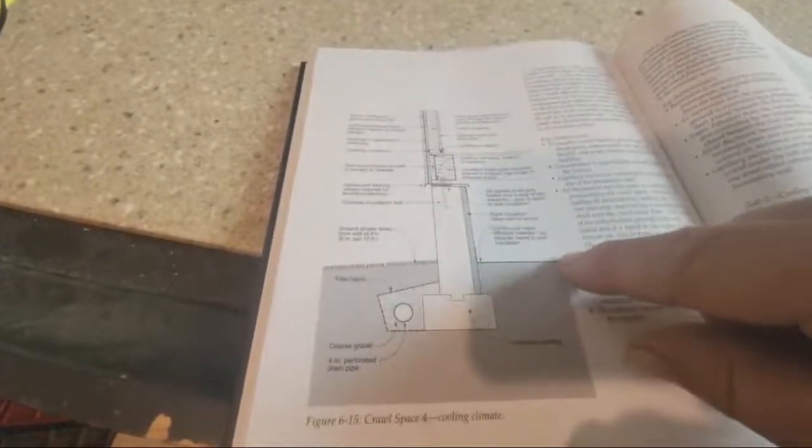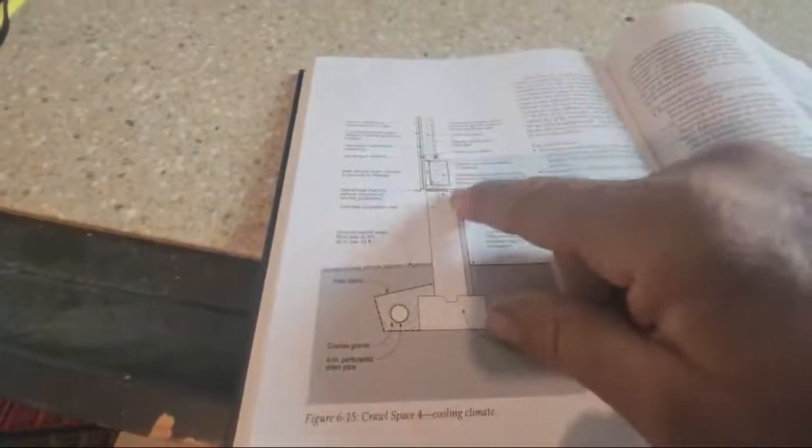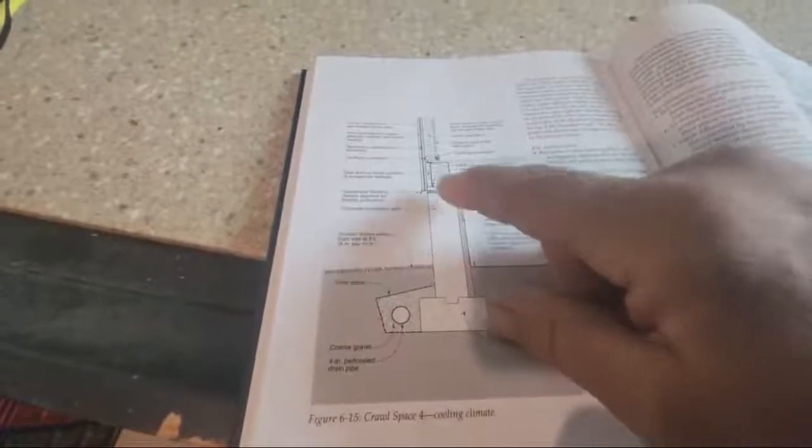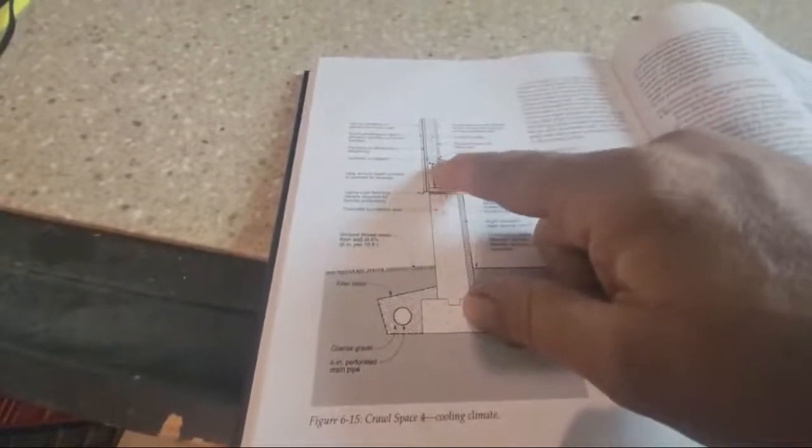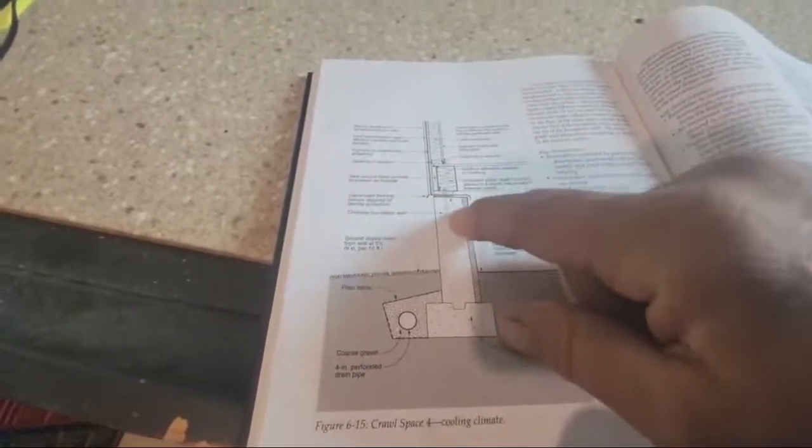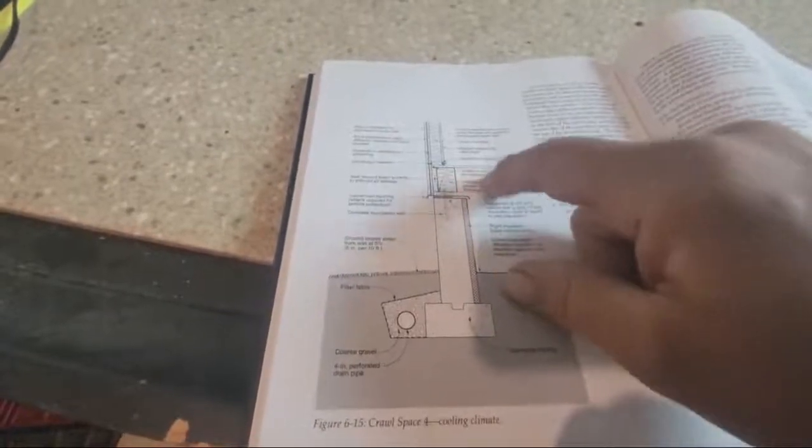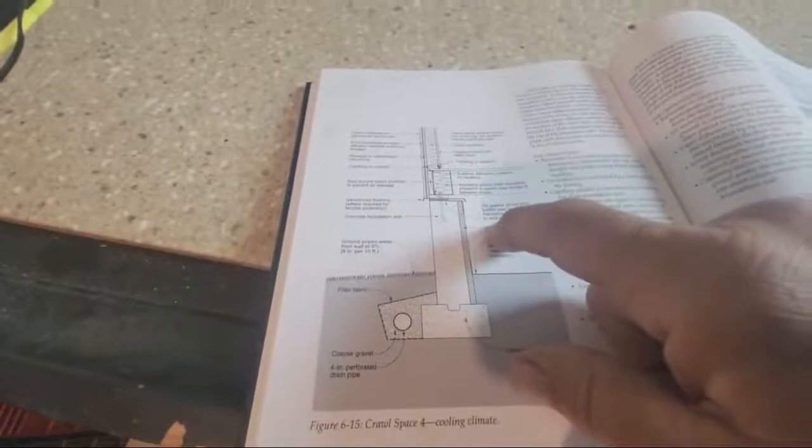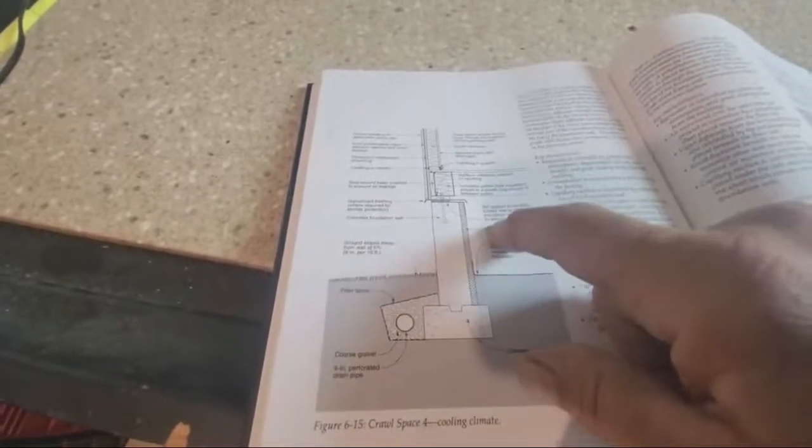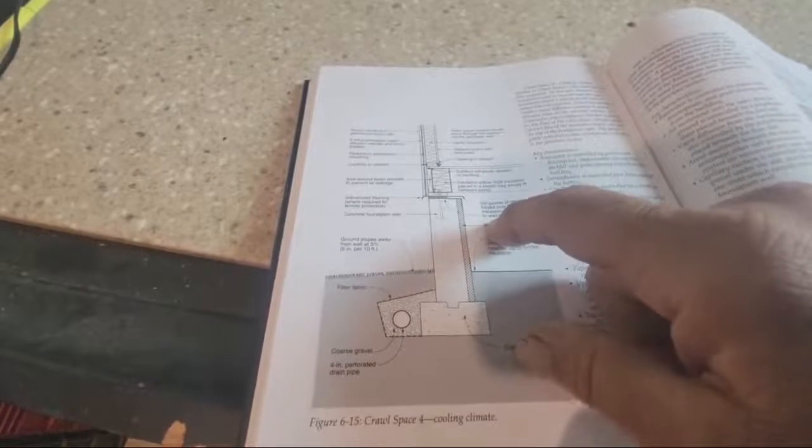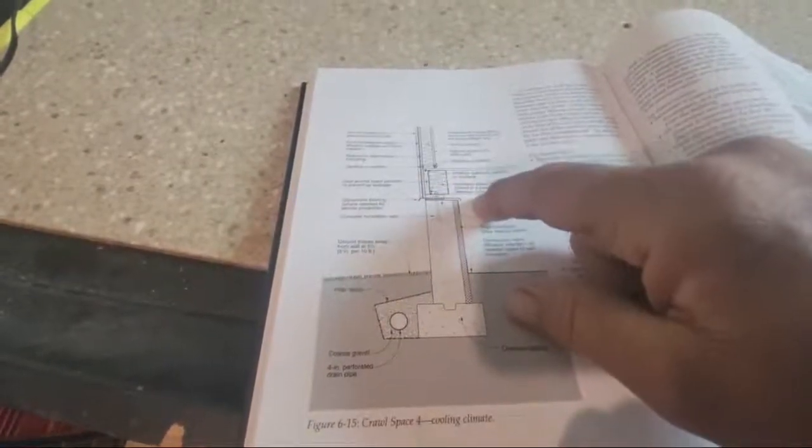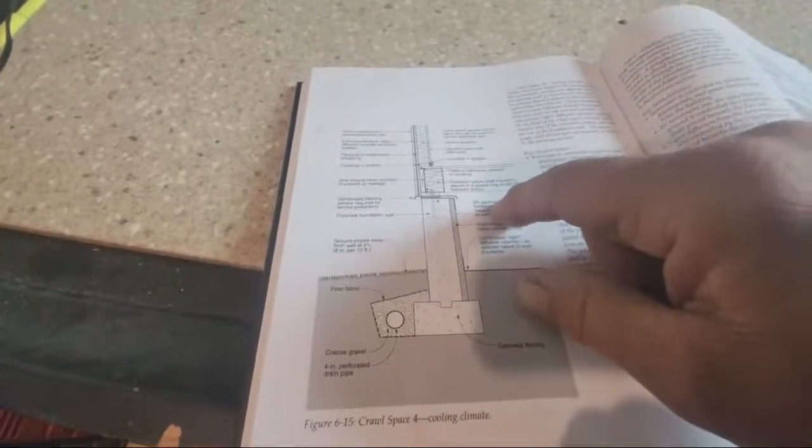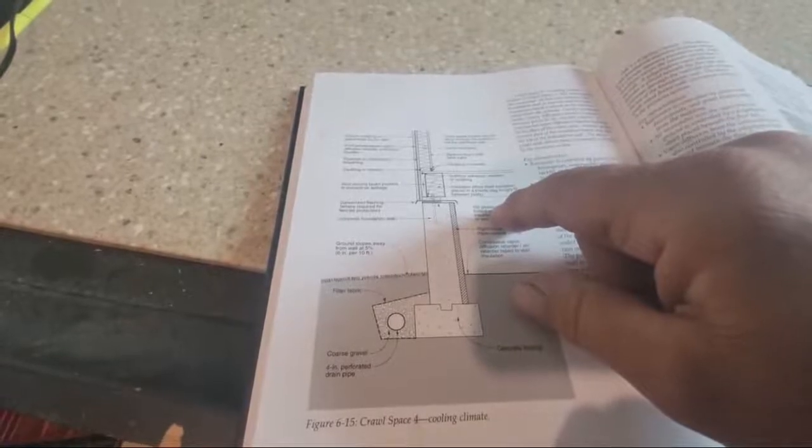The key issues are 100% sealed vapor barrier, perimeter insulation, insulation in the band joist pockets sealed, no insulation between the floors, conditioning with heating, cooling, and dehumidifying, especially dehumidifying when necessary in the crawl space. Then if you need to put a passive vent in or a register or do an HVAC balance, you could do all that as well.